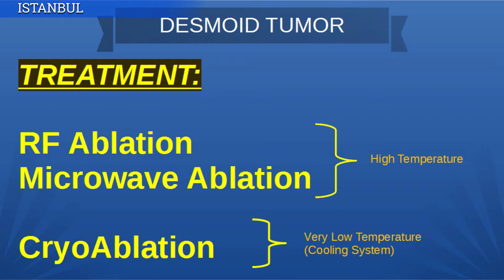We can easily say that while using RF and microwave ablation, we are burning the tumor, burning the tissue. On the other hand, in cryoablation, we give very, very cool temperature. We are freezing the tissue by using cryoablation, so we call it a cooling system, unlike RF or microwave ablation.